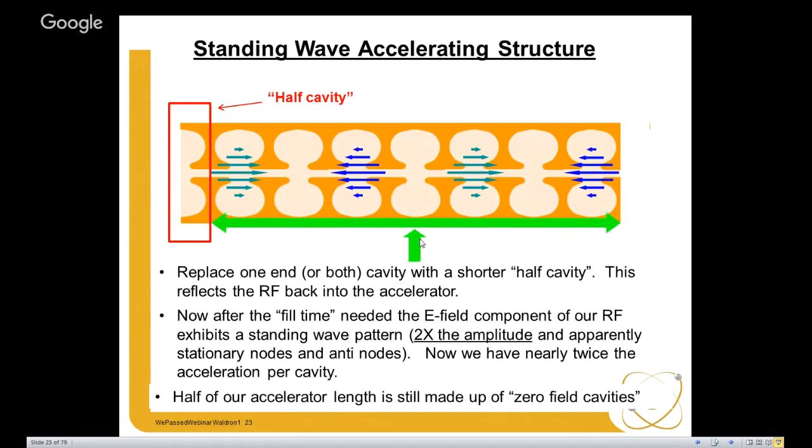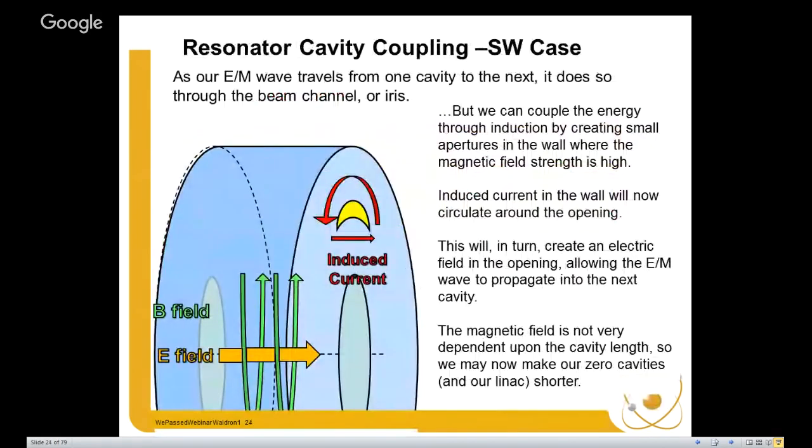And in the standing wave accelerator, it doesn't matter where we feed the RF in. It's quite popular to have the input feed be at the halfway point or at one third of the length of the accelerator. So let's go back to our cavity, our idealized can-shaped cavity. In the traveling wave accelerator, the electromagnetic waves are coupled through the central iris.